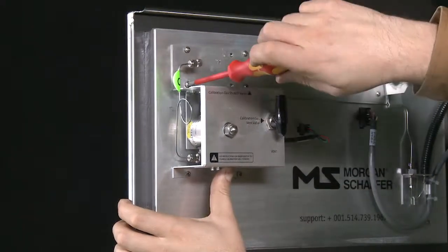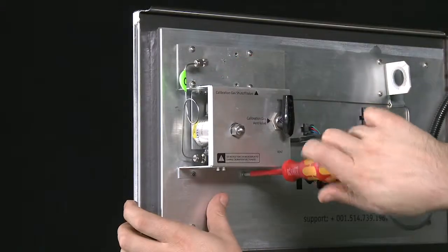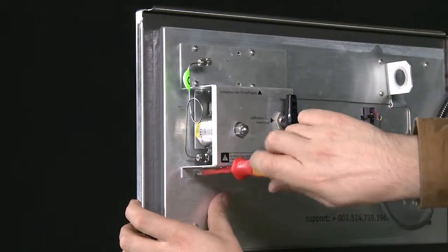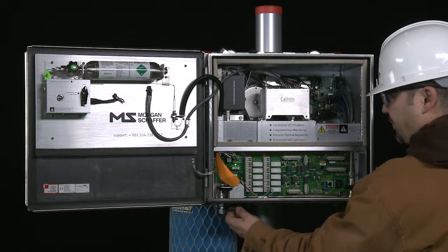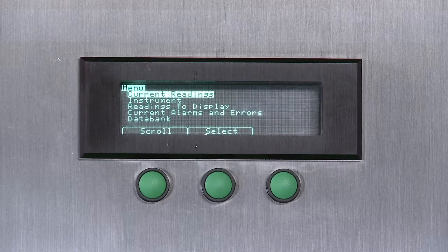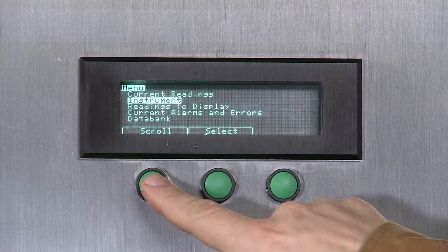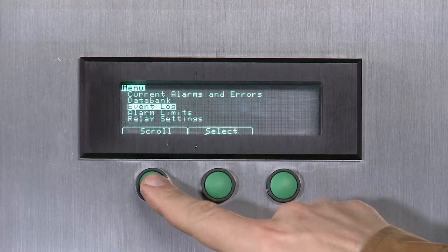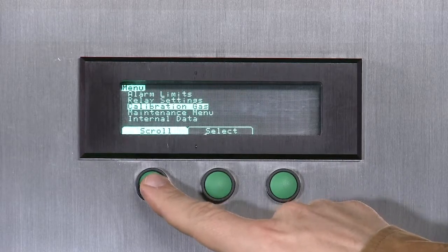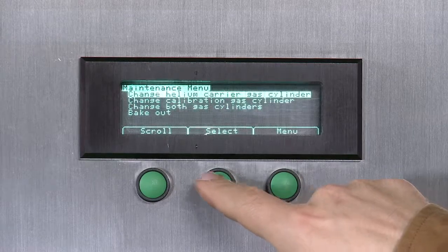Complete screwing the 6 screws, holding the calibration gas module in place on the door. Power up the Calisto. Once the display menu is illuminated, navigate to the Maintenance menu and select the option for Change Calibration Gas Cylinder.